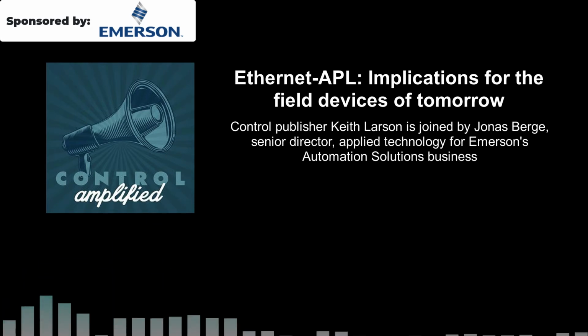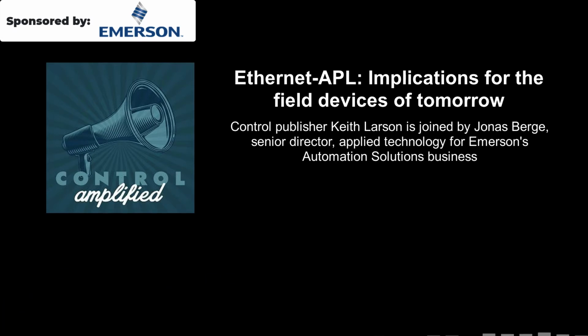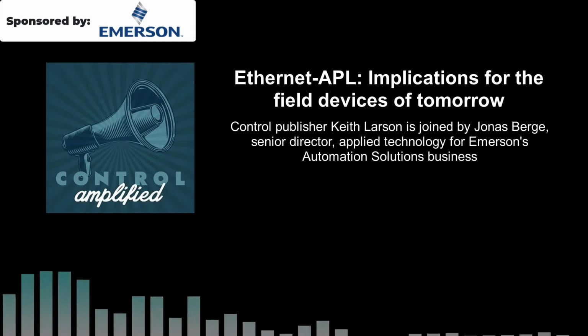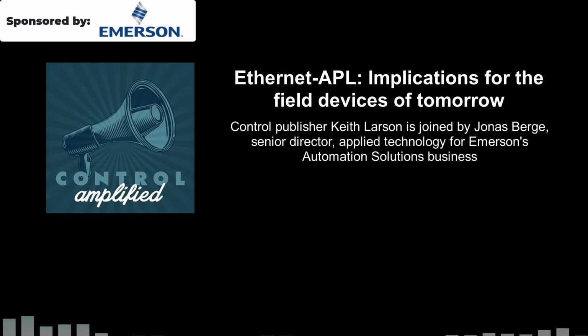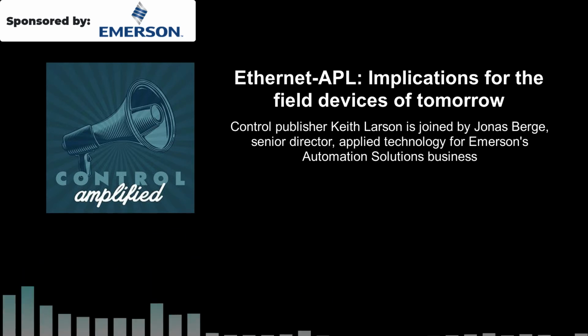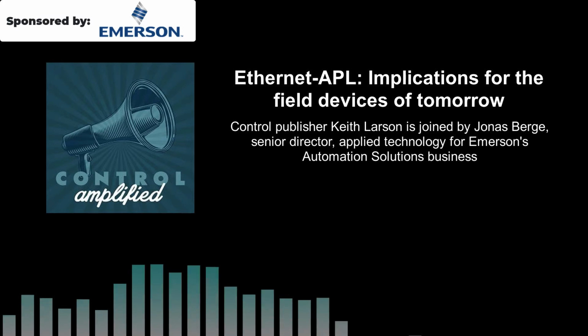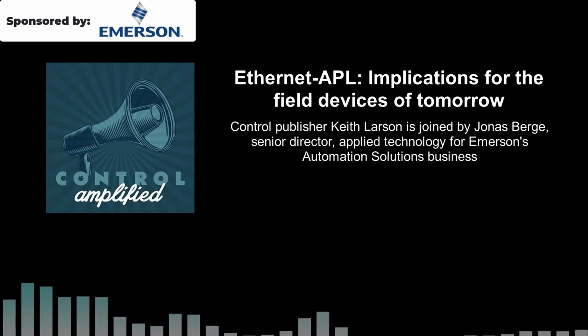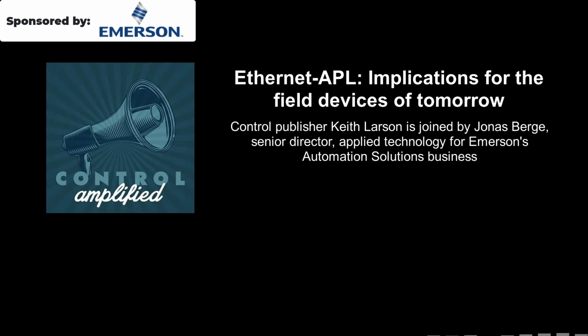Maybe just to start things off, perhaps you can talk a little bit more about just how much more bandwidth and power we're talking about with Ethernet-APL. I think people talk about the bandwidth and it's going to be faster, but compared to analog 4 to 20 milliamp HART or even fieldbus technology, there's a lot more power that's reaching the instruments as well.